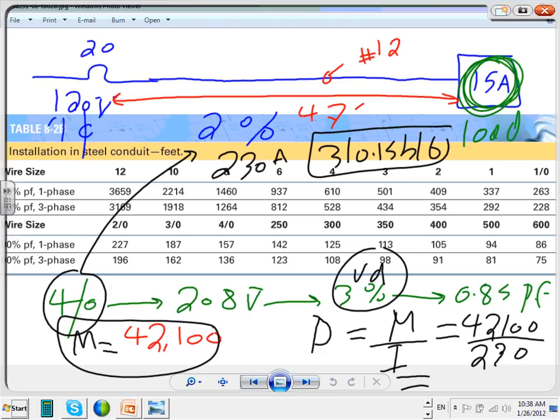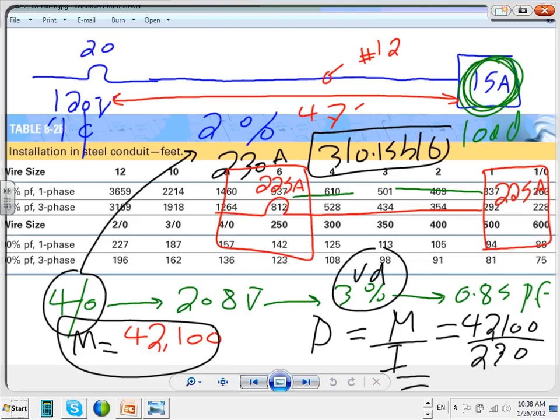So what we're doing here is really, here's my source, and this is my sub panel. Here's my 225 amp sub panel. This is the 225 amp feeder. And what I'm trying to size here is the distance from here to here. This is my main panel. There's other things coming out of it, of course. How far? What's the number? 183 feet. So this table will give you how far you can put this panel from the service at the amps that you decided to use, which is the full amp of the conductor.